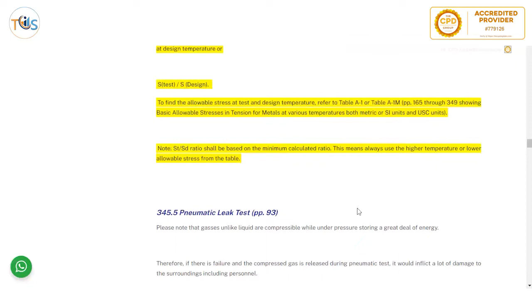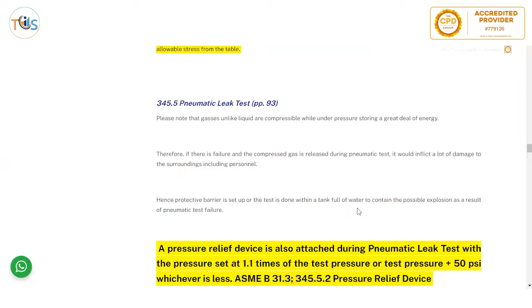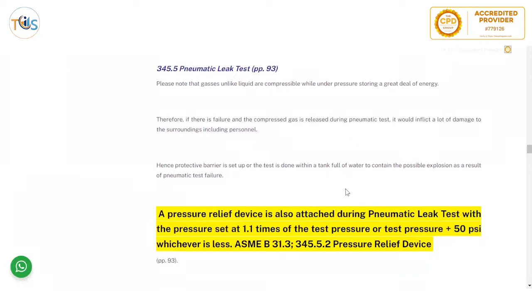So if there is any failure during the leak test or pneumatic test, especially pneumatic test, it would work like a bomb. It would be a catastrophe. Therefore, if there is failure and compressed gas is released during pneumatic test, it would inflict a lot of damage to the surroundings, including the personnel. That's why they always either do it under the water in the underground, or they put barriers around, so in case it bursts, it doesn't injure people.